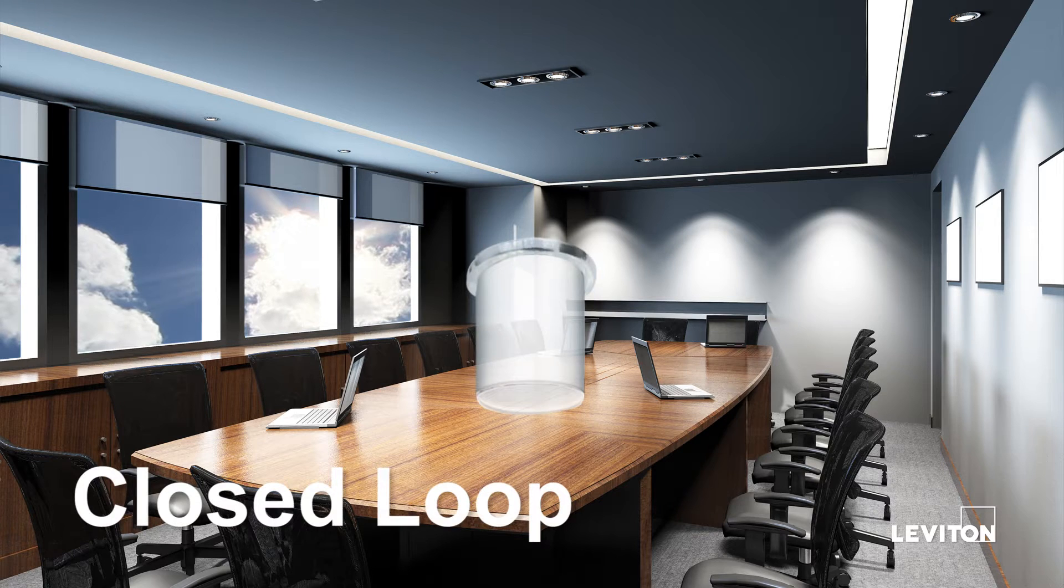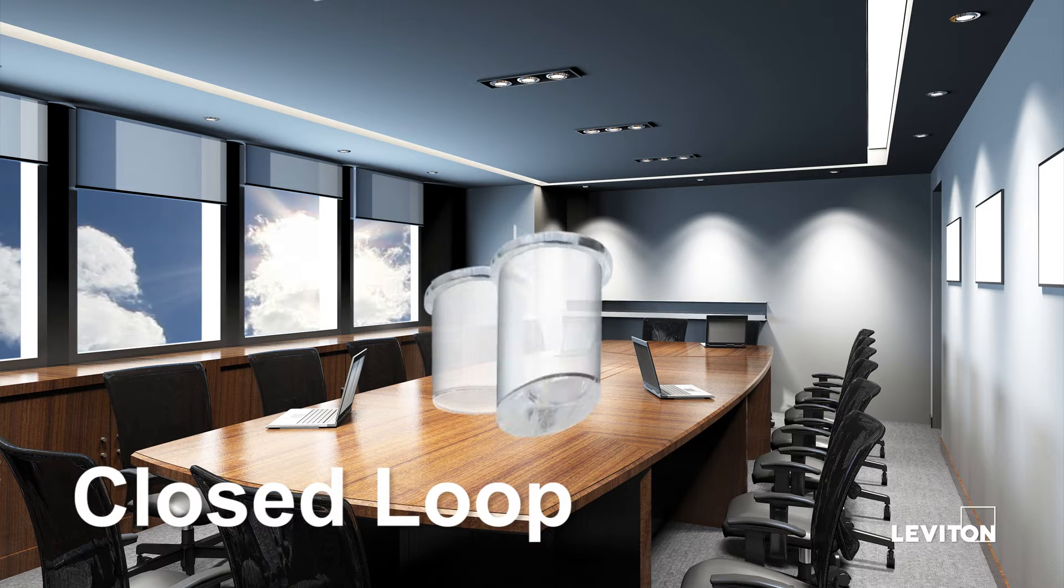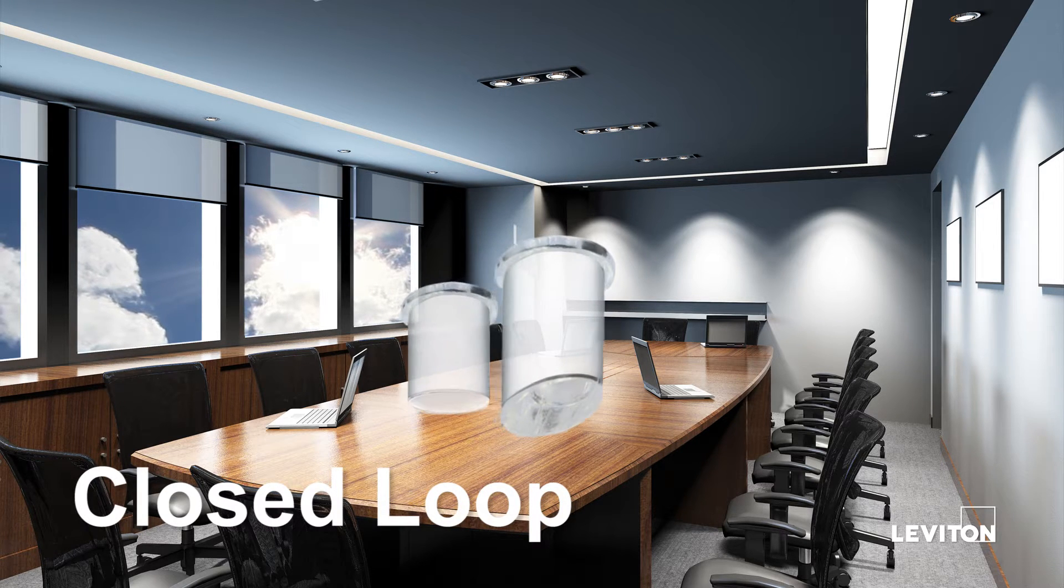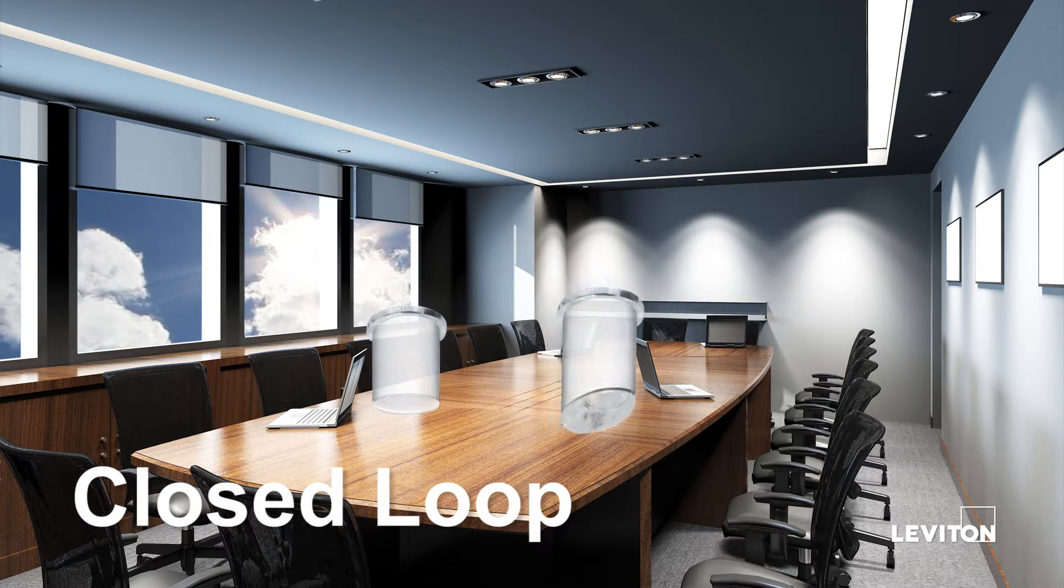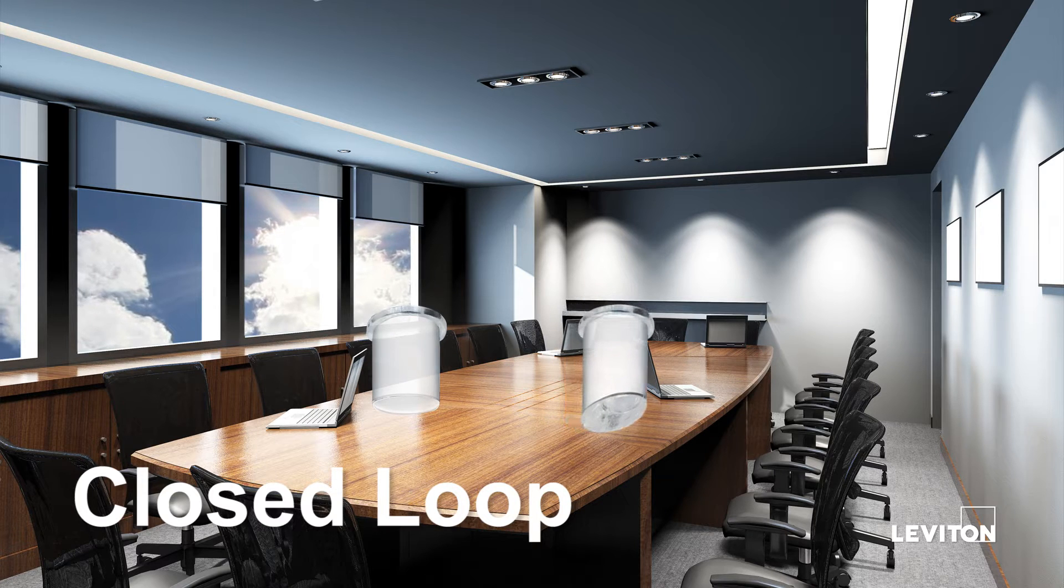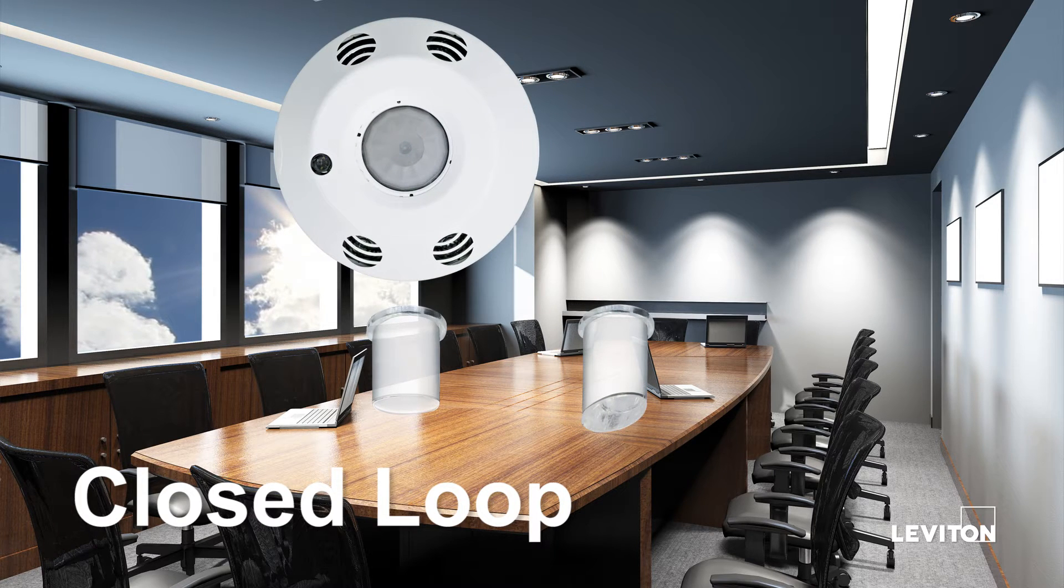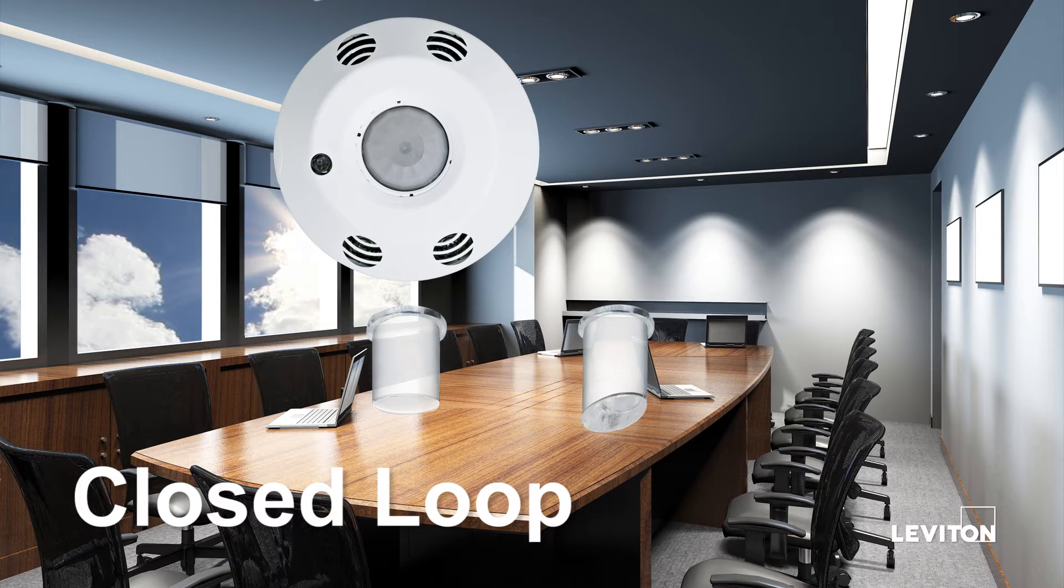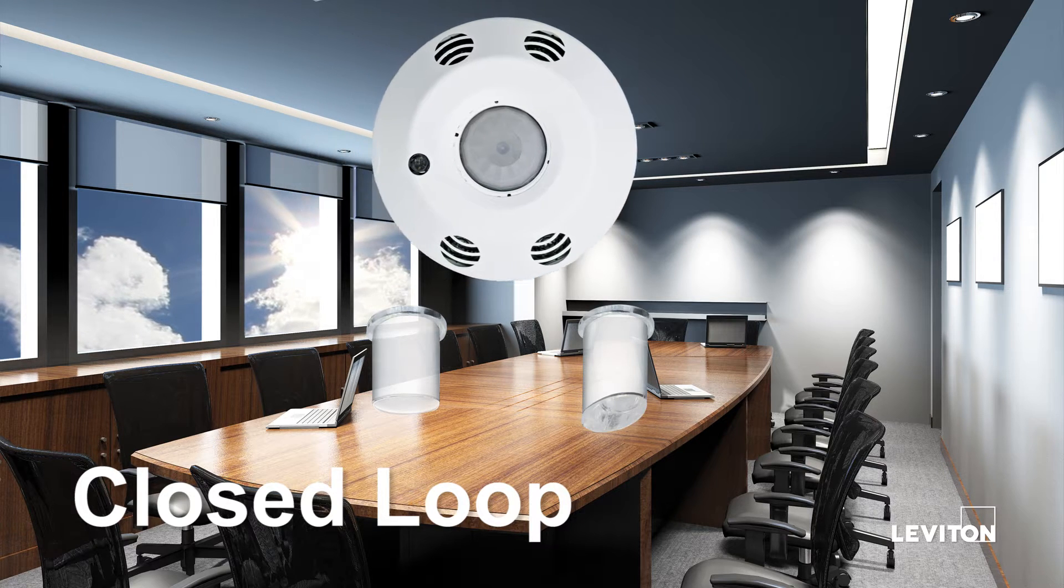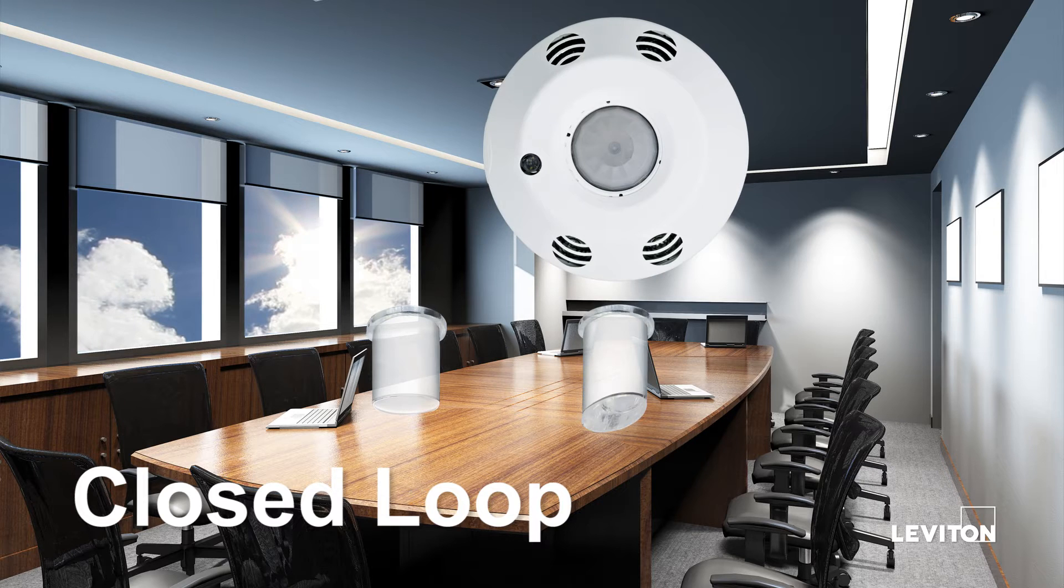Closed loop can be used with either the flat or angled light pipe. A PRC in closed loop mode with the flat light pipe should be mounted above the work surface.